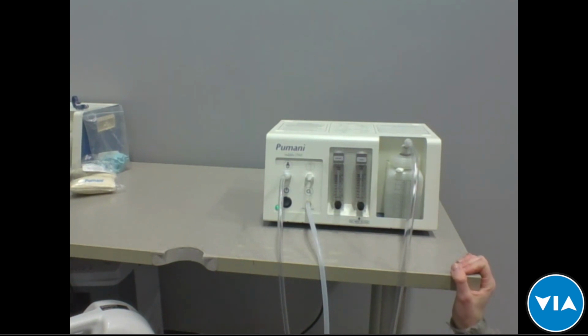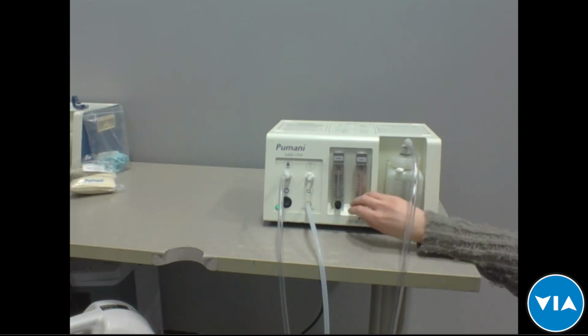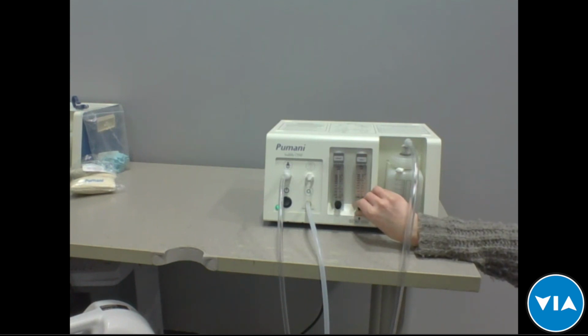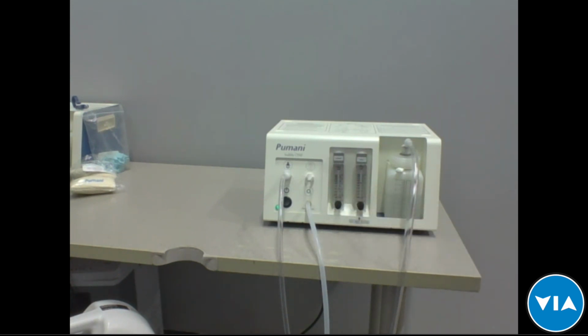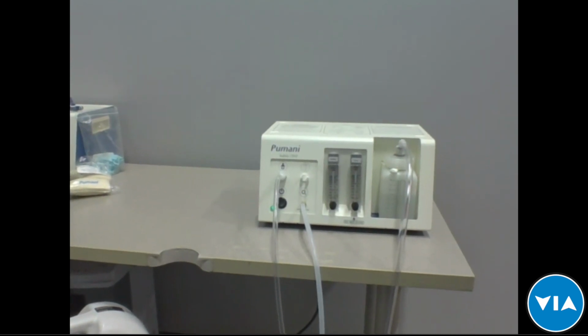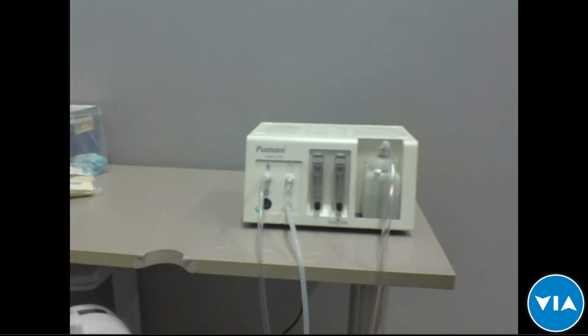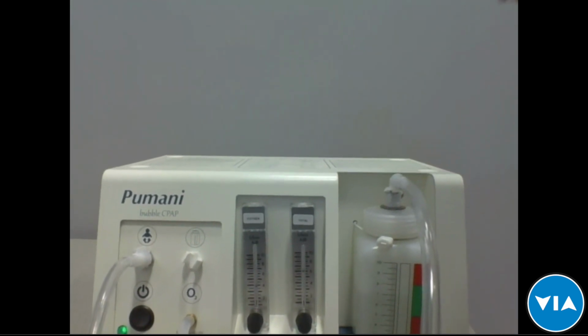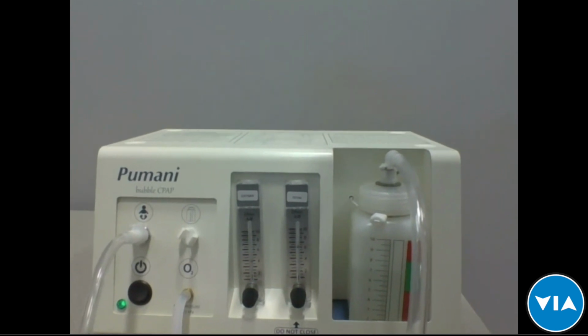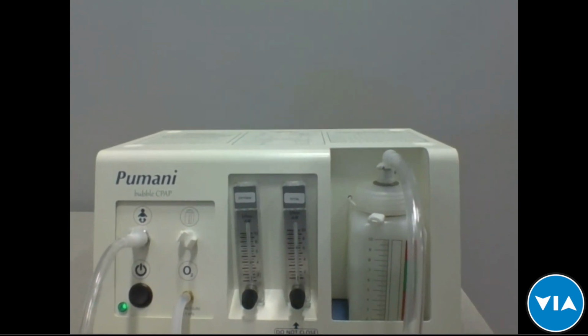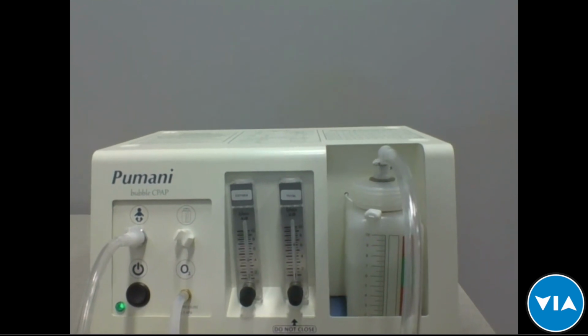Sometimes, because there are tubes and depending on the back pressure and whatnot, there can be a slight variation between that oxygen flow meter and the one on the concentrator or tank. However, you should use the concentrator or tank to adjust the flow, but what you read on the oxygen flow meter on the Pumani is the actual flow that's happening. Similarly for the total flow, that is the actual flow that's happening. The total flow is the end, so the air gets blended and goes to the total flow. If you see there, it's at 6 liters per minute. That is how much flow is going out of the patient port and into the patient.